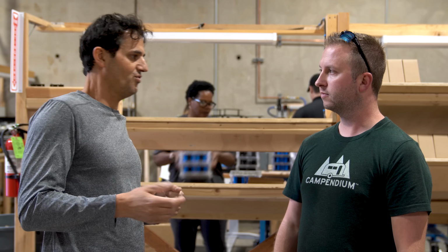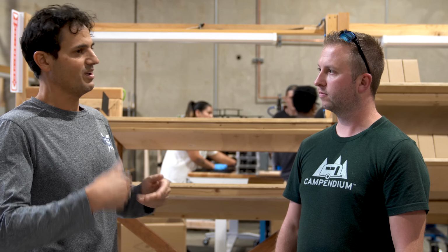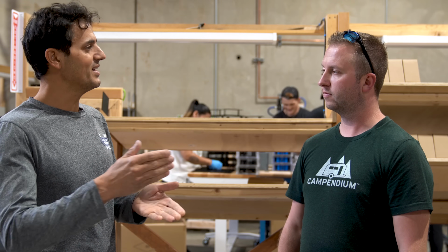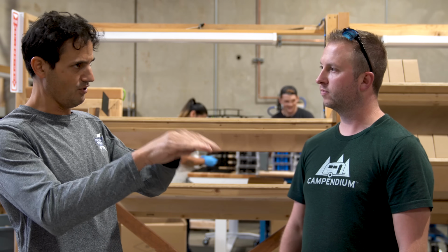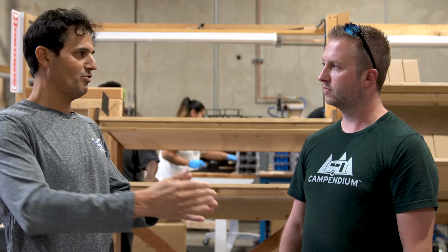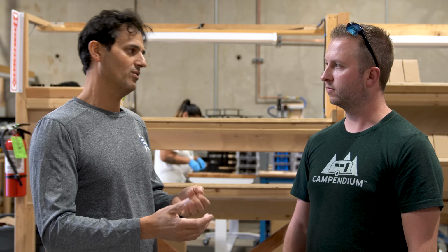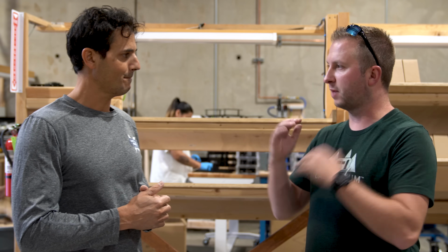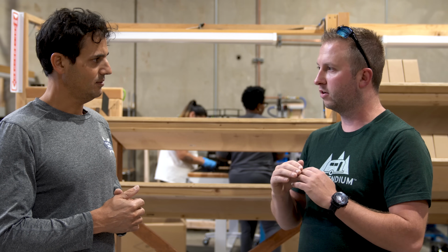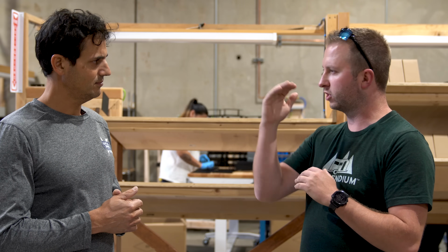There is some degradation. For example, if you're cycling, we've measured in our in-house testing that the 20% degradation, so once you go from 100 amp hours to 80 amp hours, happens somewhere between 3,000 and 5,000 cycles, depending on temperature and charging current. So in other words, if I took a battery and went from 100 down to 0, repeatedly, after 3,000 to 5,000 cycles, I would have lost about 20% of used capacity.